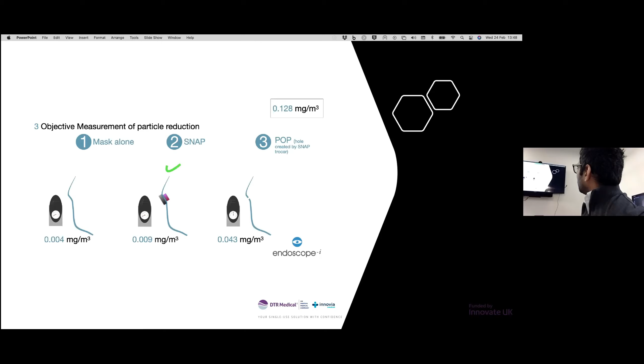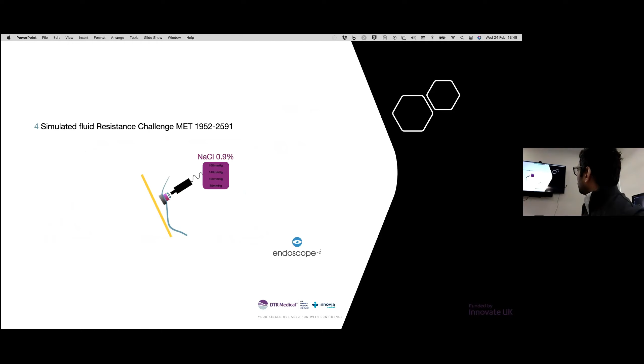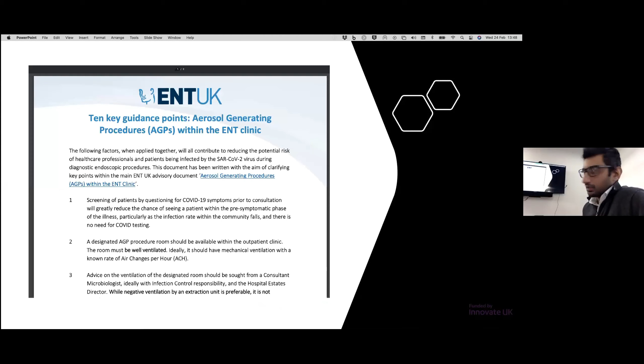And then in terms of the fluid resistant challenge, we sent our SNAP valves over to Met, who performed the fluid resistance challenges you saw for the type 2R mask, and they created a known protocol. They actually tested us up to 160 millimeters of mercury, so way beyond the test standards. We didn't measure it with blood, we measured it with saline because it would be finer, and also because we don't expect there's any bleeding with nasendoscopy. So Met designed that protocol specifically to say that would be more suited for testing the valve.